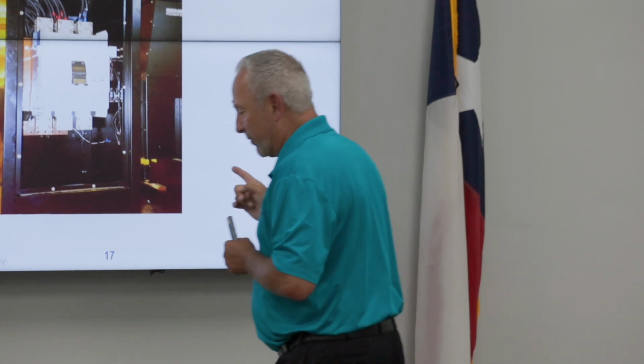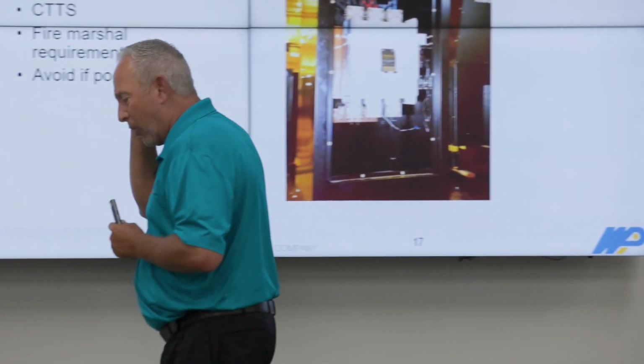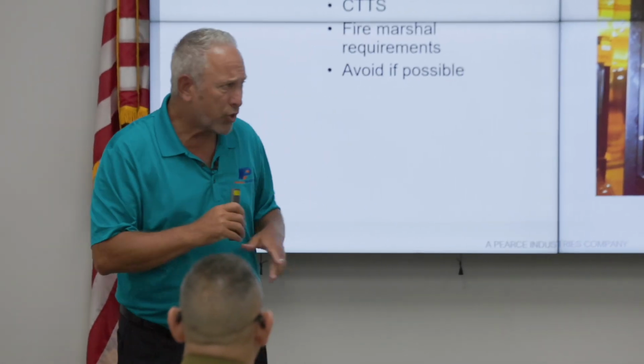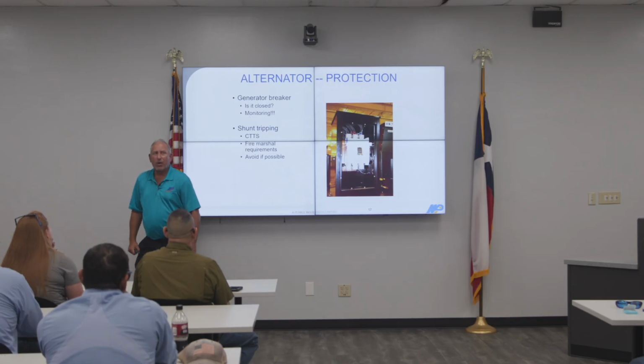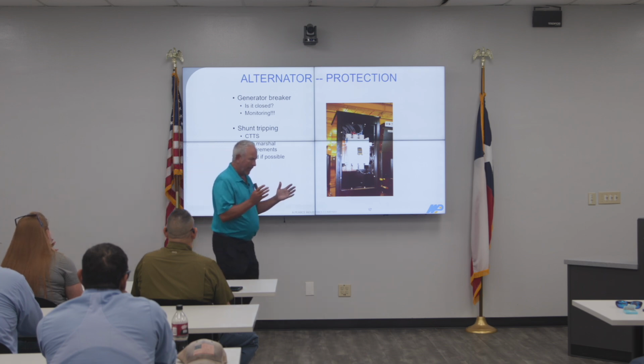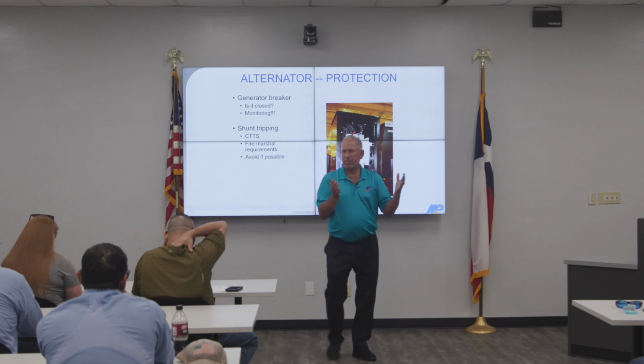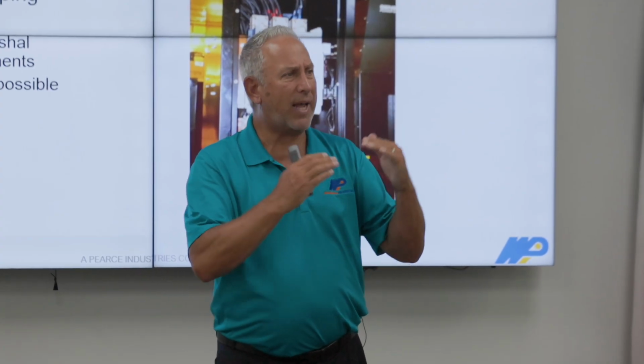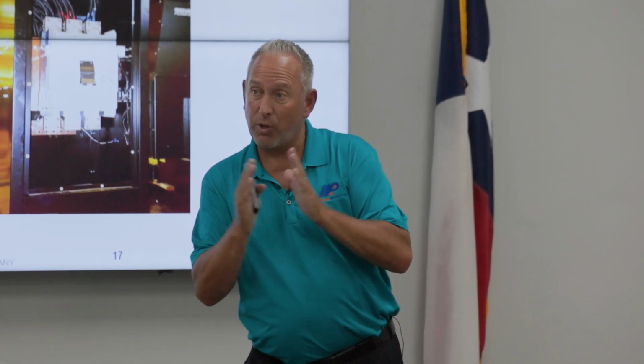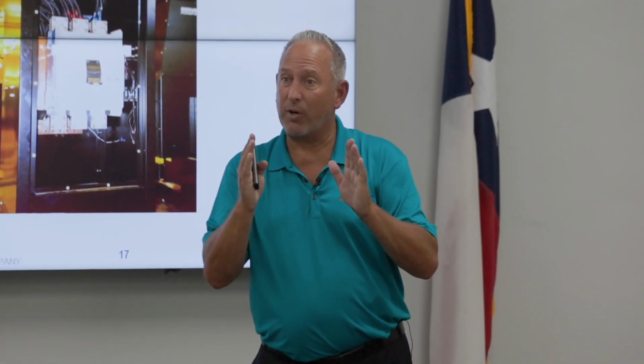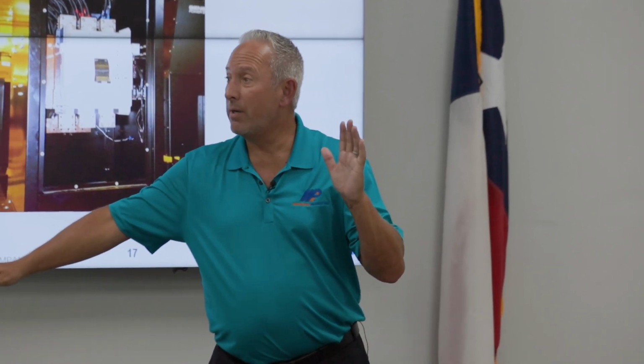Now, another reason to have electronic trip is they make what they call a closed transition transfer switch. That's what this is, CTTS, or an overlap transfer switch. So basically, a generator transfer switch sits out there and it monitors the utility's condition, right? So it's from there you set your exercise time, you set all that in that switch. So that switch goes, okay, I'm watching the utility. Utility is now out of specification, for however long you set it to be out of spec. And then the generator or the ATS will tell the generator to start, right?